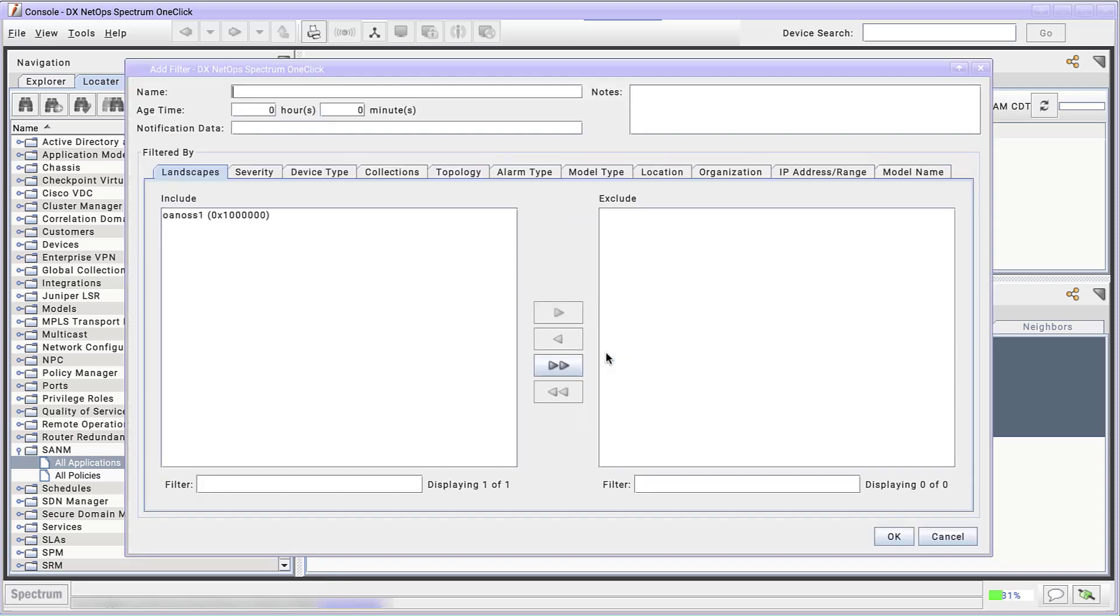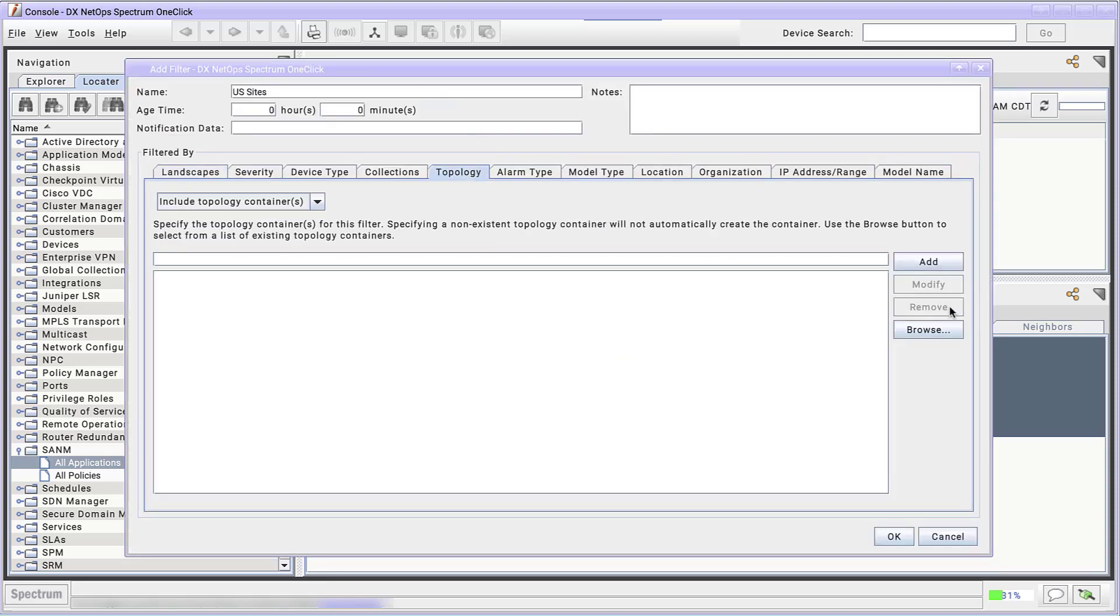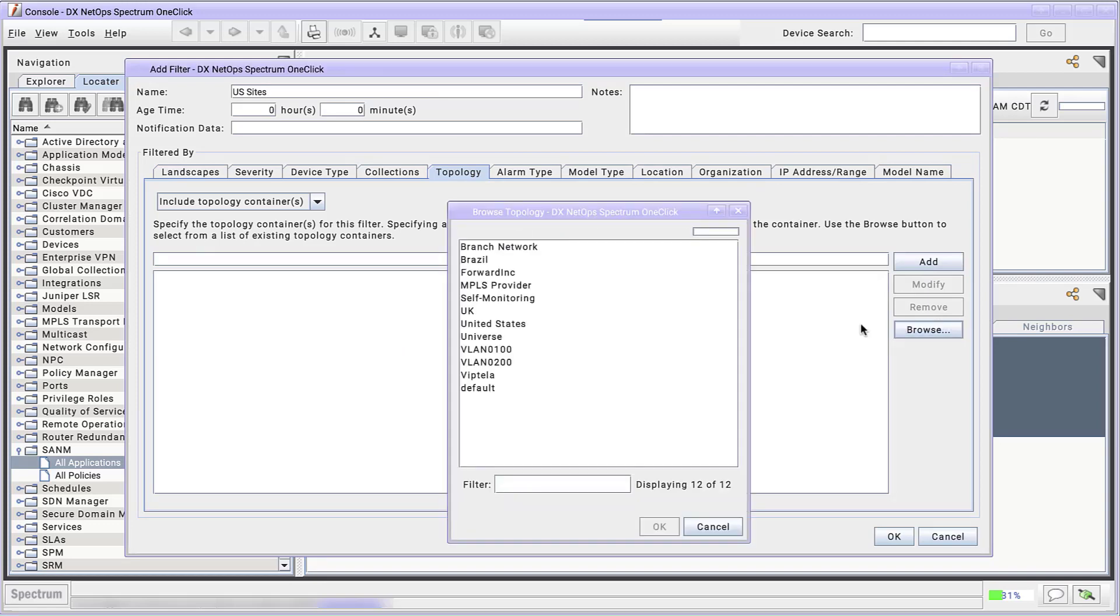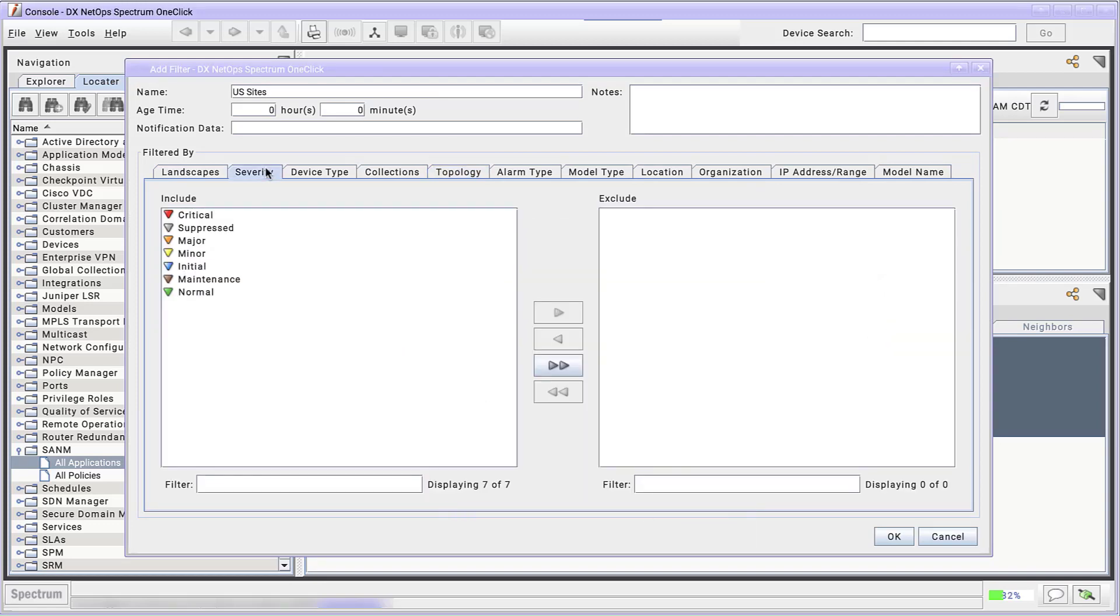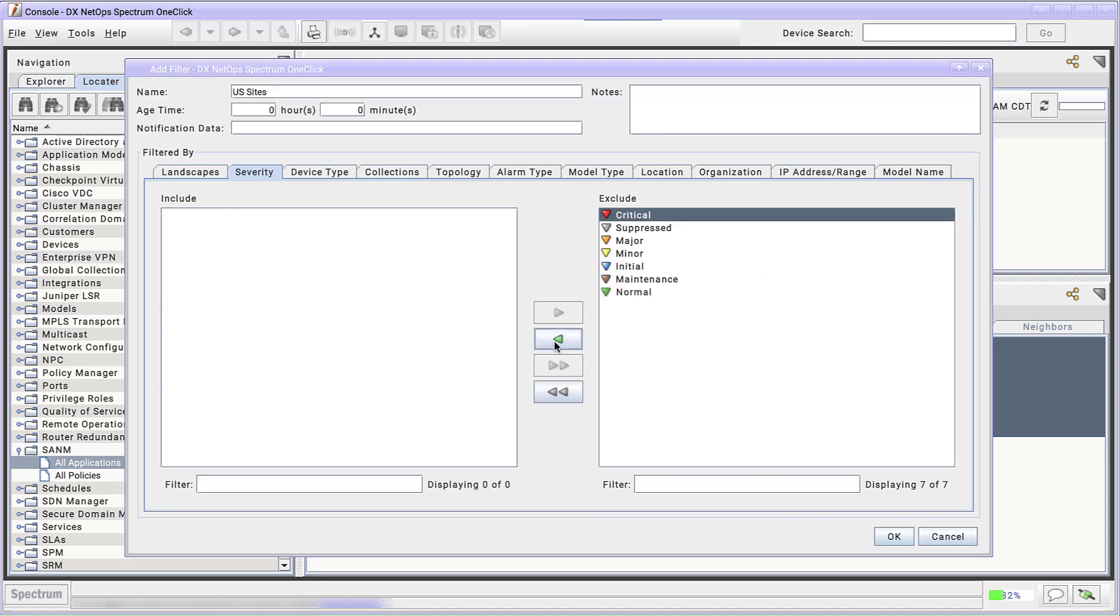We click Add to add a new filter to this policy. Click the Topology tab, then click Browse. Select United States, and click OK. Then click the Severity tab. Click the double arrow to move everything into Exclude. Then select Critical, and click the single left arrow to move it into Include. Now we're excluding every alarm severity except critical alarms.